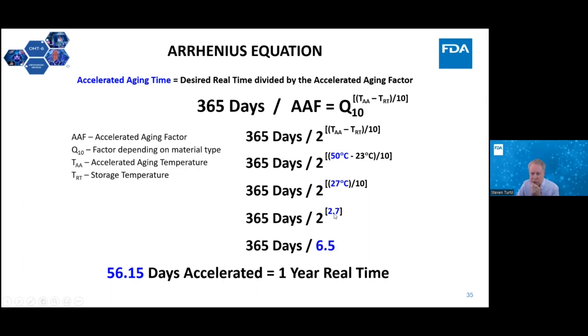2 to the 2.7 power is 6.5, divide 365 by that, and then your accelerated aging time is going to be 56 days. It's going to take a little bit longer to be 1 year of real time. And if you go up to that 60 degrees, and I've seen somebody do this once and they did have problems because they had a materials compatibility problem with that particular temperature. 60 minus 23 gives you 37, divided by 10 is 3.7, 2 to the 3.7 power is 12.99, divide 365. So that helps you do it a little quicker, but it's a delicate balance. You're going to get advantages and disadvantages however you approach this.